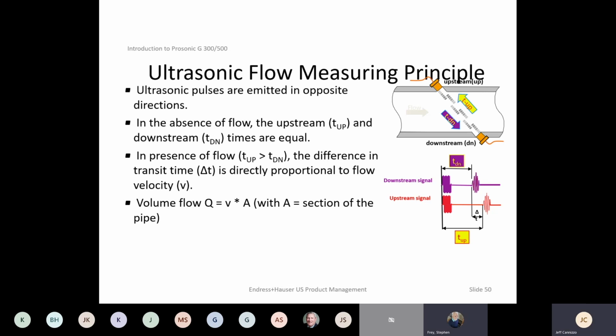And then the last technology, we talked about ultrasonics a little bit, and transit time. Transit time technology has been introduced to gas, and we've just recently introduced a new gas flow meter that uses ultrasonic technology. Basically with transit time, pulses are emitted in opposite directions. In the absence of flow, at zero flow, the upstream and downstream transit times are equal. As soon as you start to flow, the difference in the transit time between the upstream and the downstream is directly proportional to the flow velocity. And of course, we know the area of the pipe of the meter, so we can compute volume flow.